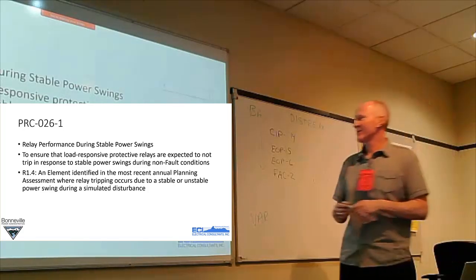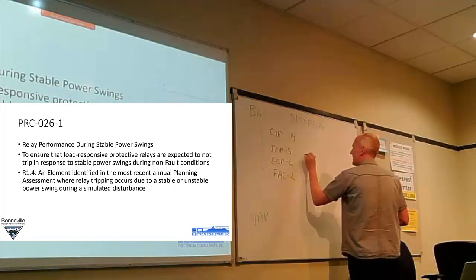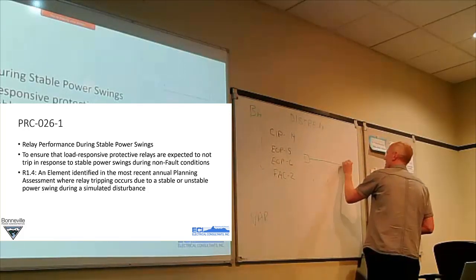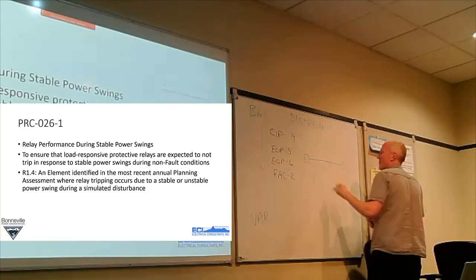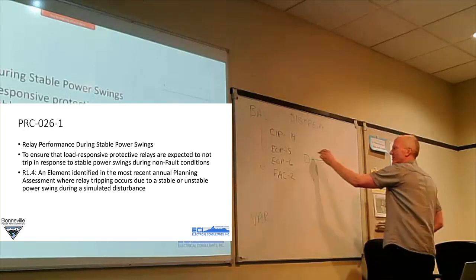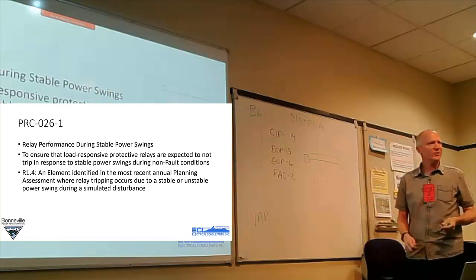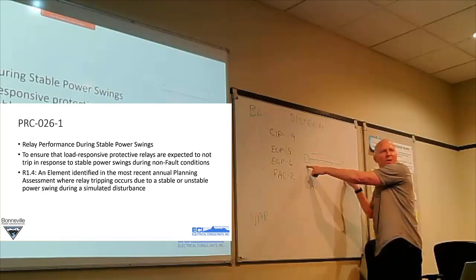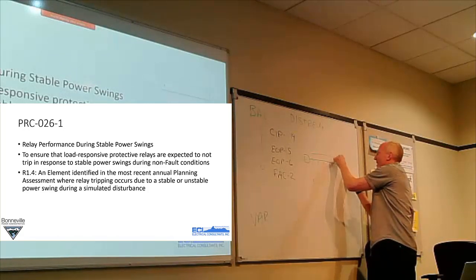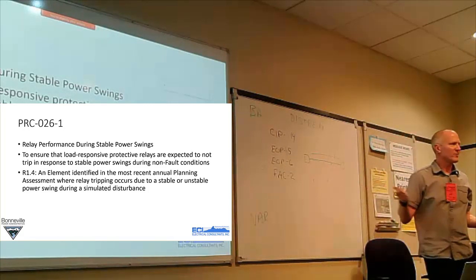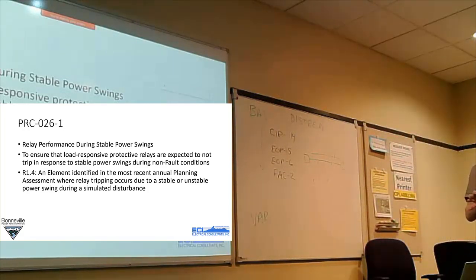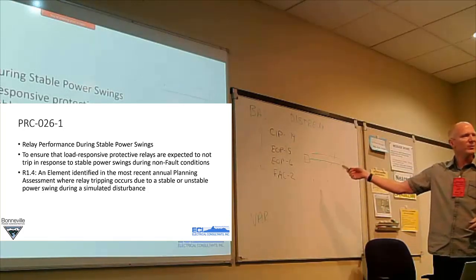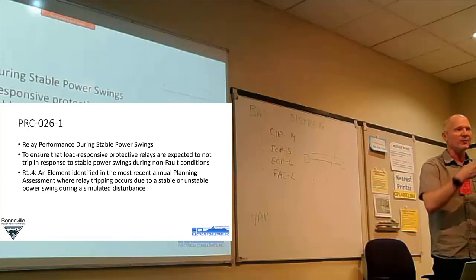So the distance relay just looks from, in this case, I know there's a bunch of other nonsense in there, those intermediate buses that PowerWorld thinks are lines, but you can add this impedance up, and you can tell the distance relay that's the impedance breaker to breaker. I want you to go at 80%, and it does zone distance, zone A, zone B, you can trigger all that stuff. It's fascinating.